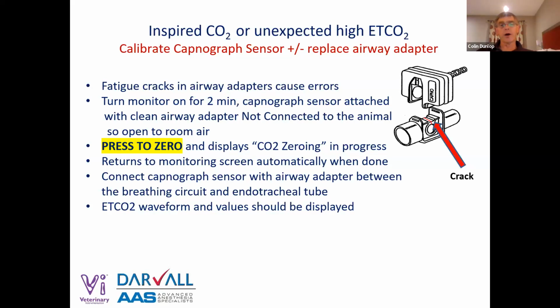You do need to zero or calibrate main and side stream capnographs. And if you've got a mainstream sampler, that's the little airway adapter here. If they develop a crack across the top, which is a fatigue point in those adapters, the light travels through that crack and it's not going to read properly.